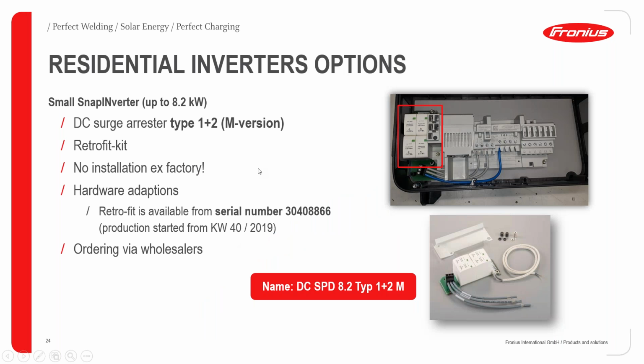So having said that, we also have residential inverter options, which include DC protection, DC surge protection, which comes in the Type 1 and Type 2 version. It is a retrofit kit, which means we don't have it ex-factory, so it's an optional accessory. But with the need for DC protection, it's always advisable that you have it installed. All you need to do is to have the serial number and then order it from your wholesalers.